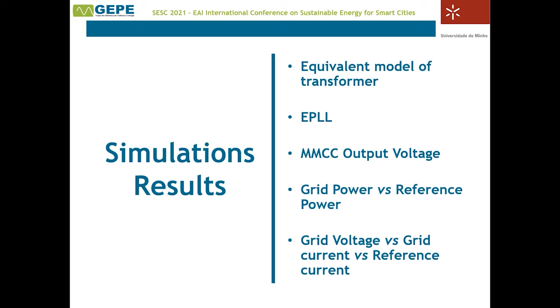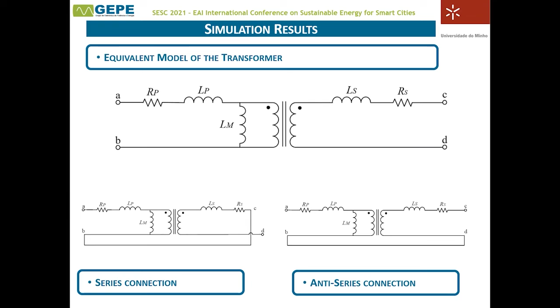It was necessary to measure with the windings in series, with terminal B connected to terminal C, measuring from A to D, and in anti-series, with terminal B connected to terminal D, measuring from A to C. When measured with the winding in series, a value of 4.9 mH was obtained.